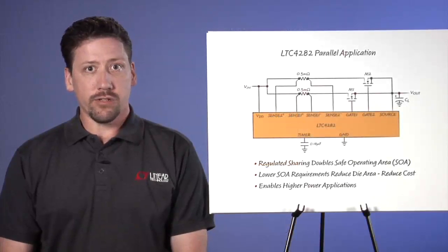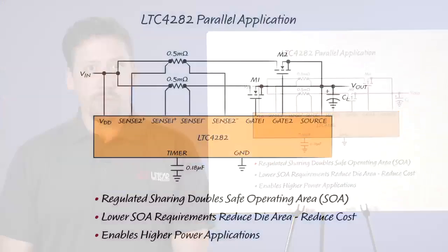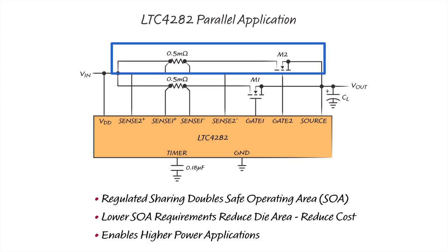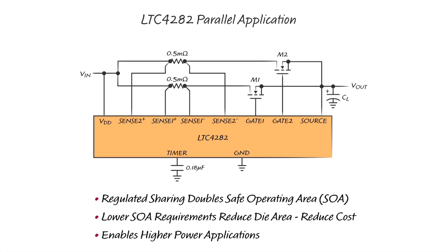The LTC4282 resolves this problem by dividing the MOSFETs into two parallel banks with independent current limits that enforce sharing between the two banks. This method doubles the SOA of an application while using the same number and type of MOSFETs as a traditional solution, allowing the use of MOSFETs with lower SOA. Since SOA is proportional to die area and die area is proportional to price, this leads to significant cost savings.